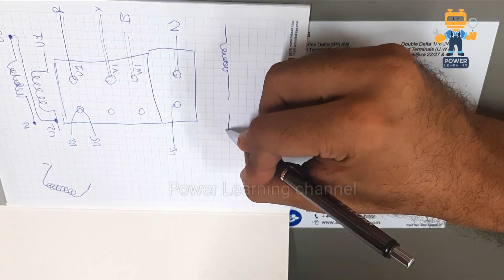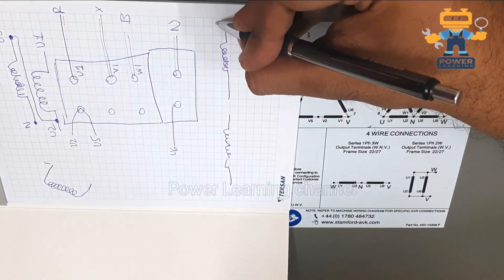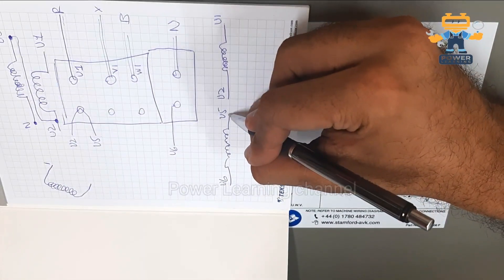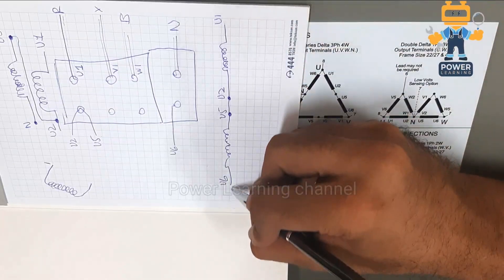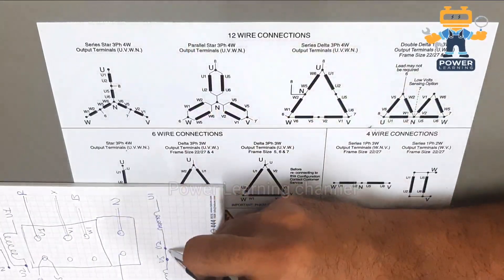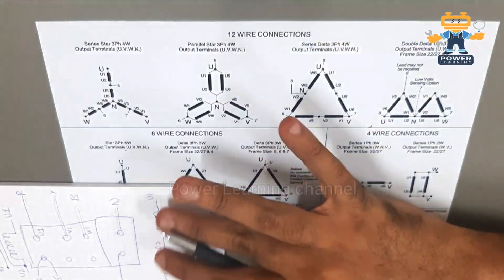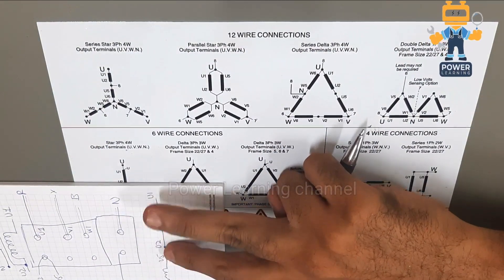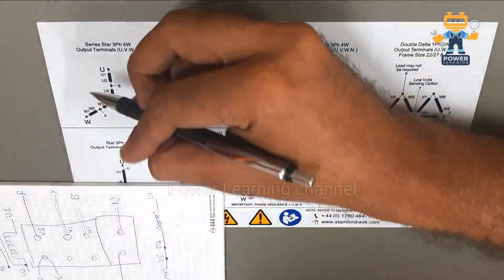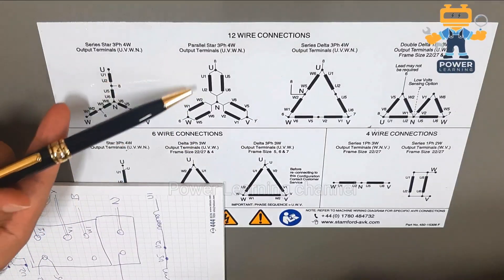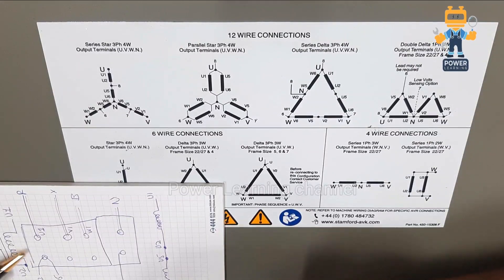To visualize: this is the first coil — u1 and u2; this is the second coil — u5 and u6. These are four separate terminals. When connected in series, the current path goes: u1 → u2 → u5 → u6 to neutral, end to end. Don't be confused by the figure showing them as single points — actually these are four terminals that merge in the diagram.